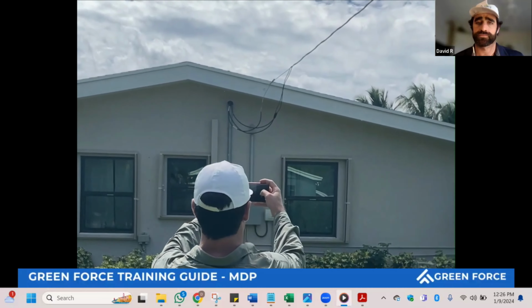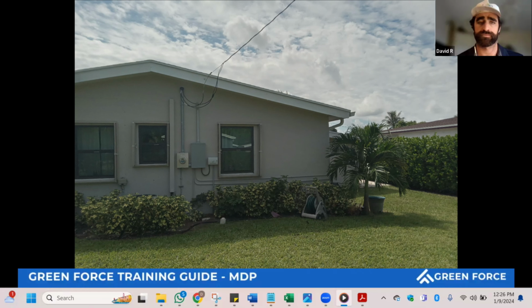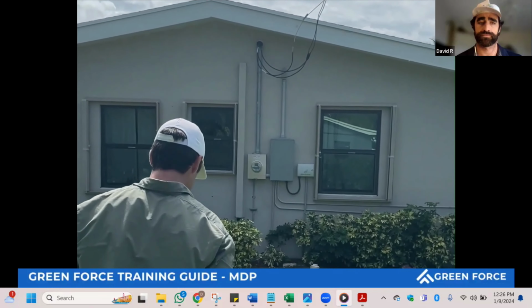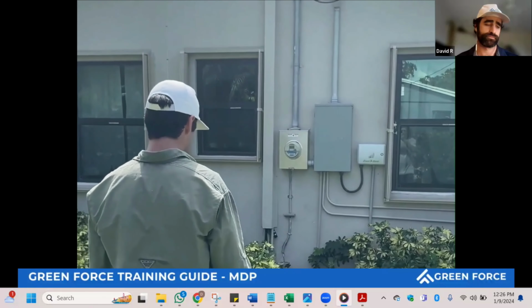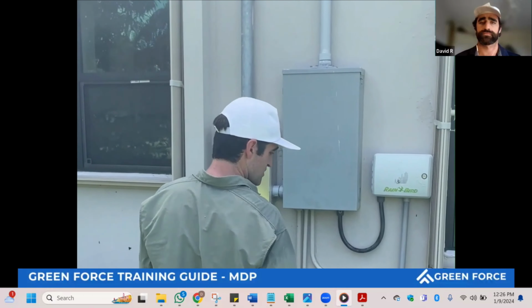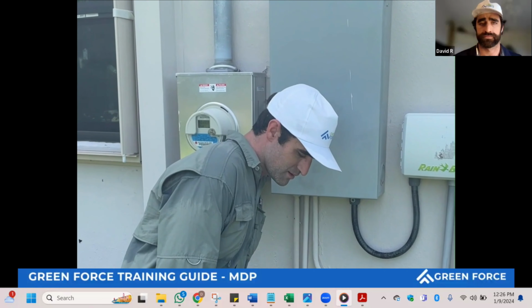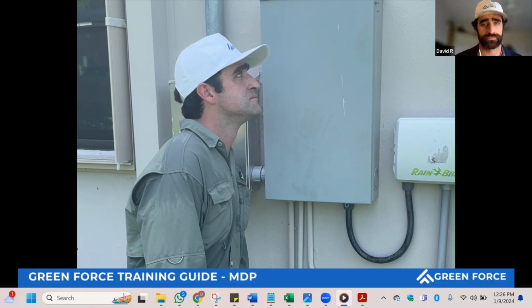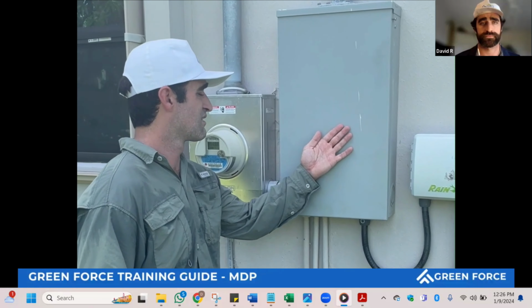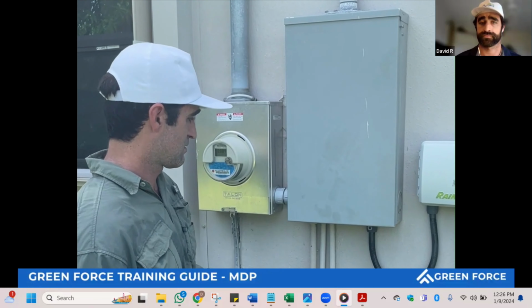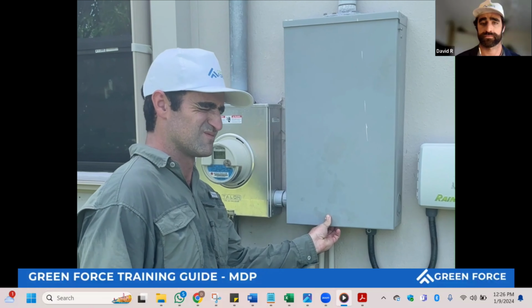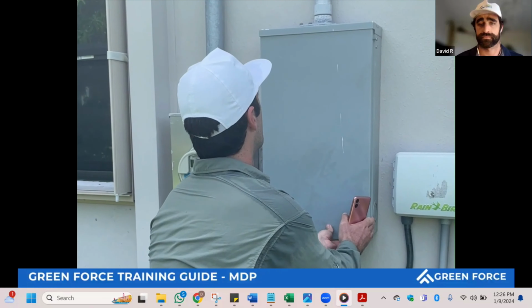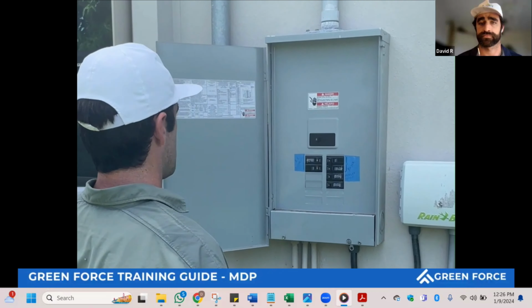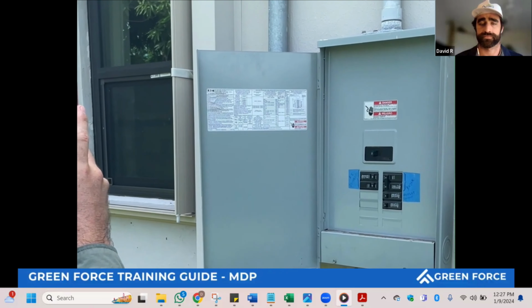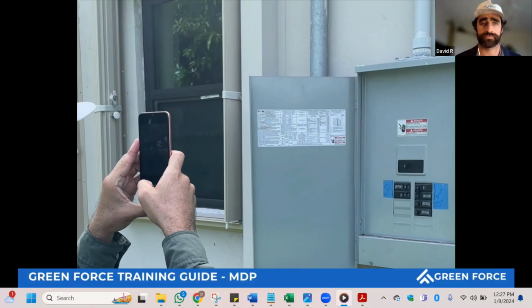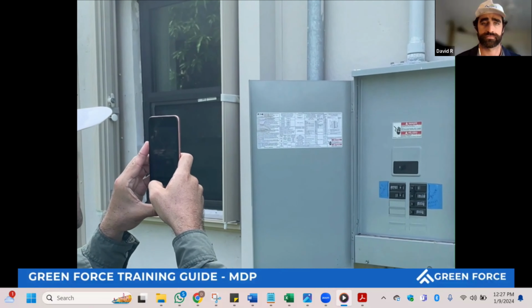We start with photos of the available wall space around the MDP. Clear space is essential to ensure safe access and maintenance. Next, engage your senses: listen for any arcing sounds and smell of burnt plastic, which may indicate a hazardous condition. Safety first - use the back of your hand to gently touch the enclosure to determine if it's energized, preventing unintended shocks. Now step back and take a photo from approximately 6 feet away to provide an overall view of your MDP.